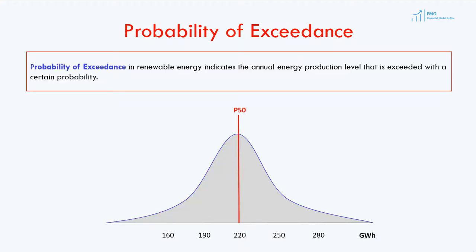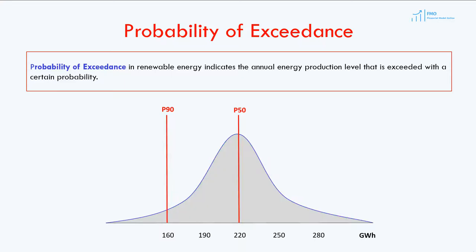A more conservative probability of exceedance would be P90, which corresponds to an annual energy production of 160 gigawatt hours. P90 means that there is a 90% chance that the annual energy production level of 160 gigawatt hours will be exceeded, and only a 10% chance that it will fall below 160 gigawatt hours. The higher the chance that a certain level of production will be exceeded, the lower the production number. The P-value can be thought of as how confident you can be that generation over the period will exceed a given value.